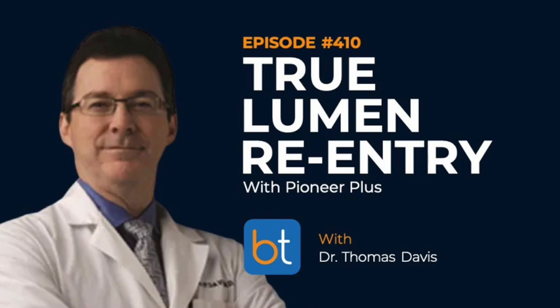So you sort of have to reorient the shaft to neutral and then try turning around again in a gentle area, because that's a frustrating thing I've seen users in my hospital do when I have to come in and give them a hand. It's, I can't get the needle to go out. It won't go out. Because you have like a wire wrap kind of. Exactly. Because you're pushing that needle out on that shaft.